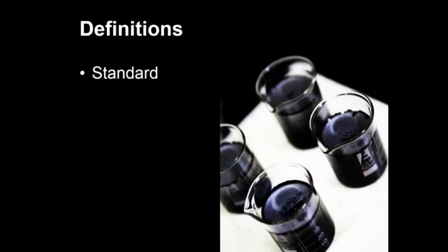The word standard refers to an ISO method or procedure, literally, but it's used to refer to a control sample and that's now well entrenched. The ISO guides refer to a reference material as opposed to a certified reference material, which is of a higher caliber, has metrological traceability and a detailed certificate of analysis, whereas a reference material, which is used colloquially to encompass all of the different reference materials, may or may not be a certified reference material. So it could be of a lesser caliber.